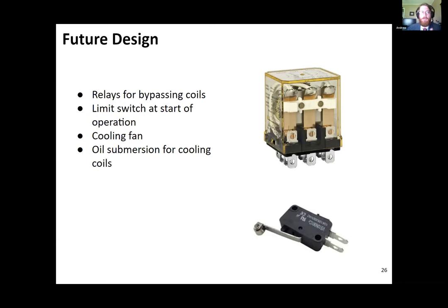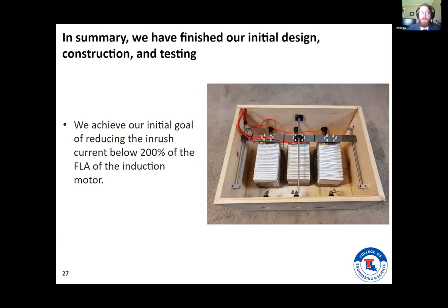But in conclusion, we did manage to reduce our inrush current to below 200% of the FLA of our motor, which was 10 amps. So we never saw above 20 amps during our testing. And we managed to make it in a package that isn't struggling to necessarily keep up with the speed of acceleration of most of our motors.